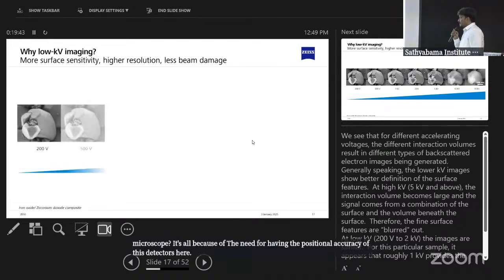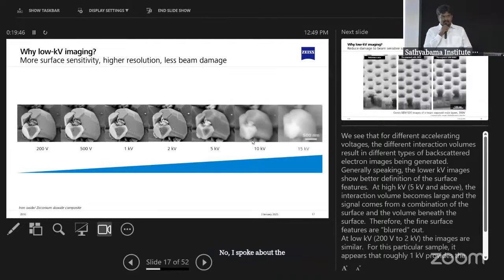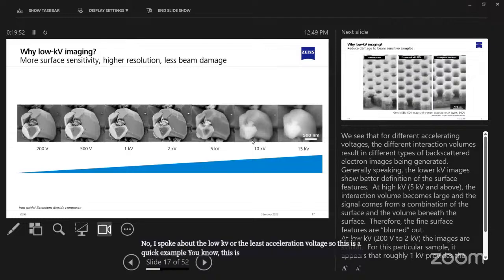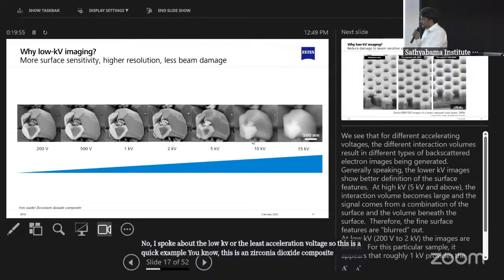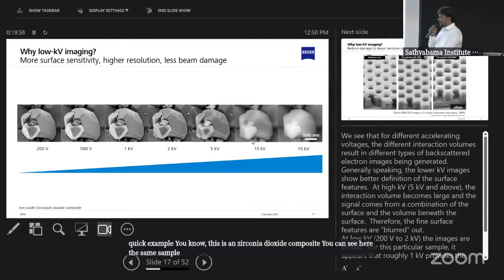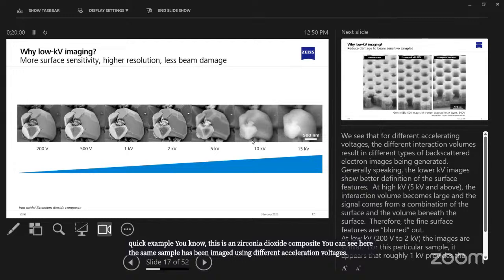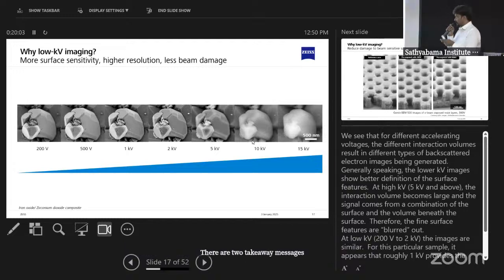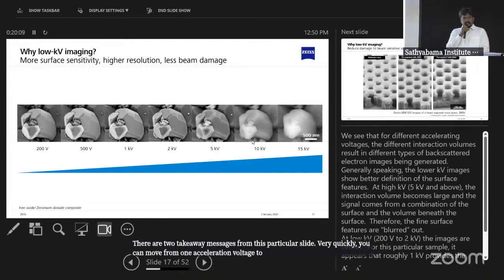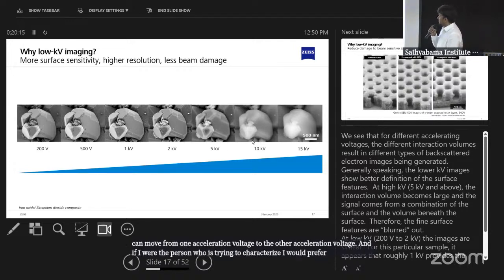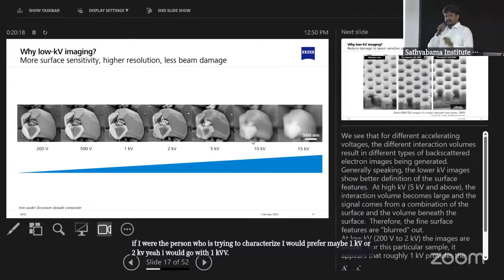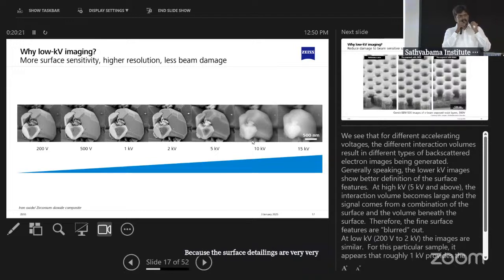Now, I spoke about the low kV, or the lowest acceleration voltage. So this is a quick example. This is an iron zirconium dioxide composite. You can see here the same sample has been imaged using different acceleration voltages. There are two takeaway messages from this particular slide. Very quickly, you can move from one acceleration voltage to the other. And if I were the person trying to characterize, I would prefer maybe 1 kV or 2 kV. I would go with 1 kV because the surface detailing is very, very crystal clear and crisp.